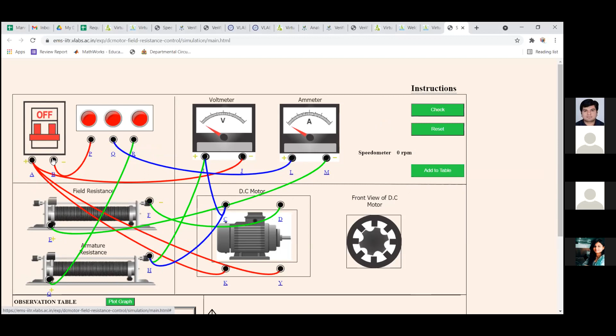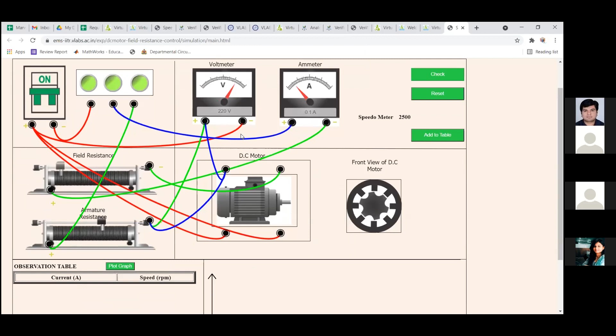If we do some wrong connection, we can click on the node values. Clicking on this blue colored P button, that particular connection will go off. So we can redo it. Once we are done with the connections, we can go for checking. Once we have the correct connections, we can go for turning on the MCB and proceed with the experiment. First we need to set the voltmeter reading. Next, we need to provide field resistance in steps. For each field resistance value, we need to click add to table. And similarly, we need to proceed further. Once we have sufficient readings, we can go for plotting the graph.